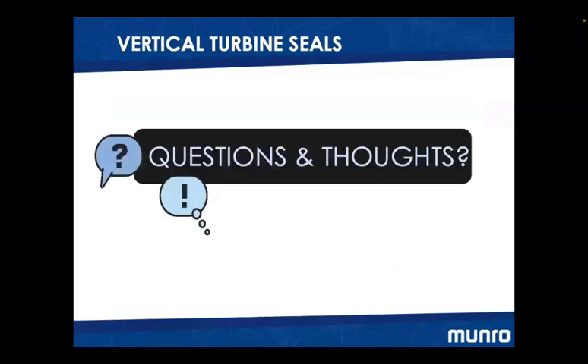Okay, any questions on vertical turbine seals and why we might select one over the other? I don't see any right now, but a quick question for me is, from packing to mechanical, it sounds like one is more of an upfront cost and one is a more longevity cost. Do you see that those typically weigh each other out, that they come out to be a wash? Yeah, typically they're going to come out to be a wash based on the required maintenance that's necessary for the packing style seal.